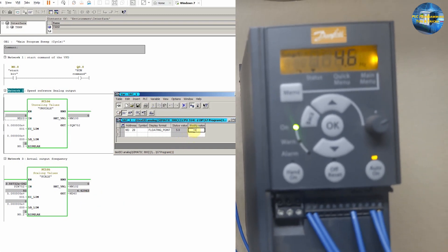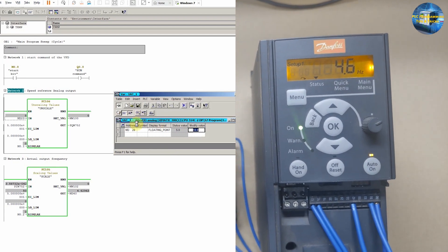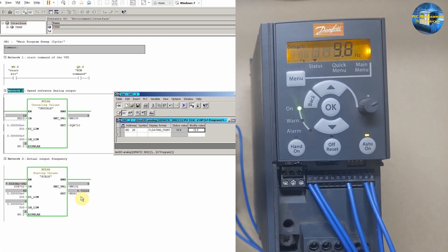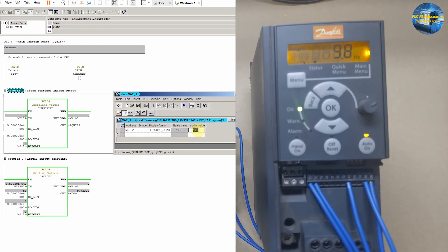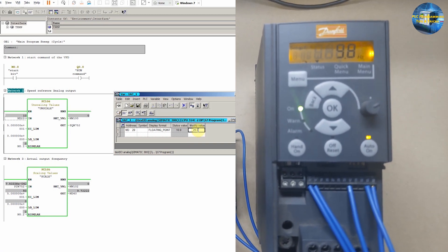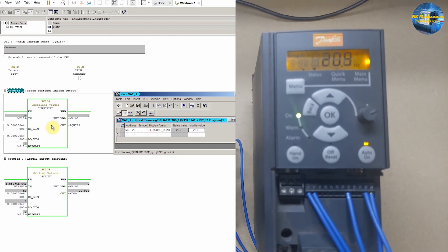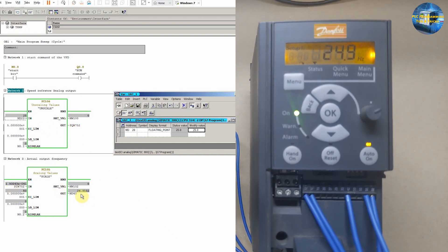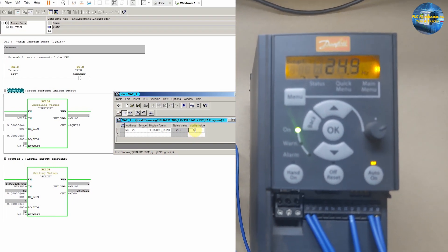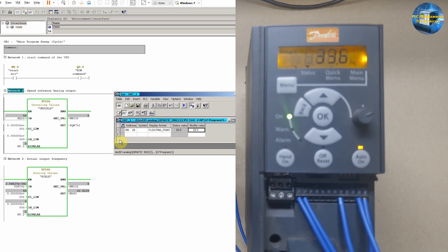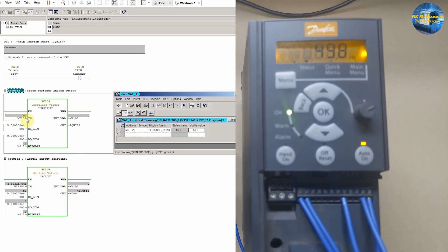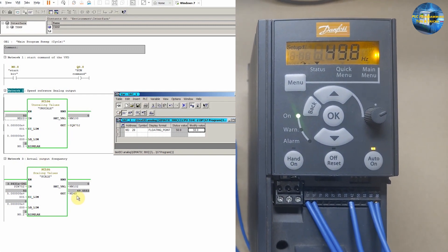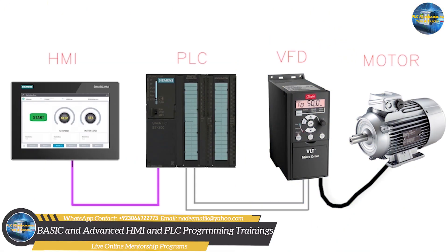Next we modify the setpoint MD20 to 10 Hz — the setpoint goes to PQW752 and the VFD runs at 10 Hz, sending back the actual frequency at 9.72 Hz. Next we try 25 Hz — the VFD runs at 25 Hz and the actual output frequency sent by the VFD is 24.9 Hz. Finally, at 50 Hz setpoint, the VFD runs at 50 Hz and sends back the actual output frequency as 49.8 Hz. That's the end of part one of the video tutorial.